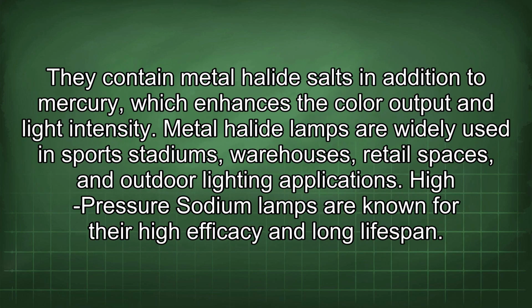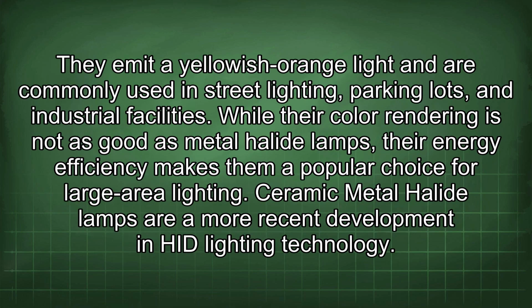They contain metal halide salts in addition to mercury, which enhances the color output and light intensity. Metal halide lamps are widely used in sports stadiums, warehouses, retail spaces, and outdoor lighting applications. High-pressure sodium lamps are known for their high efficacy and long lifespan. They emit a yellowish-orange light and are commonly used in street lighting, parking lots, and industrial facilities.